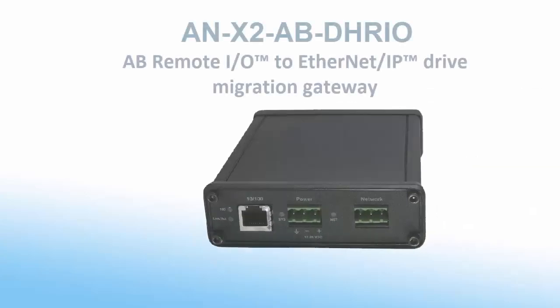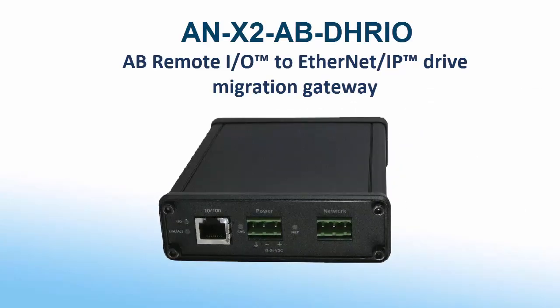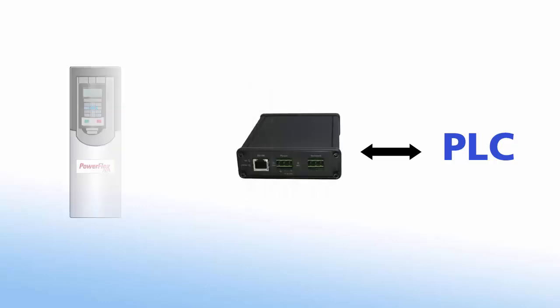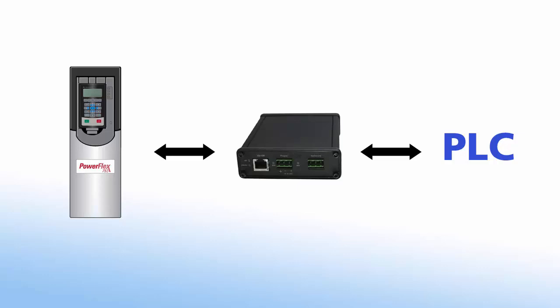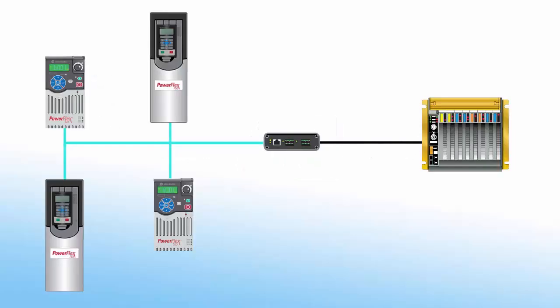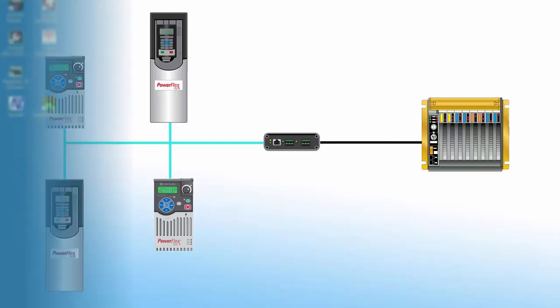In this edition, we'll be setting up the ANX2 Data Highway Remote I/O Drive Module to migrate a legacy PLC5 or SLC application with a Remote I/O Drive to a new Ethernet IP-based 753 PowerFlex drive without changing the PLC code. Each ANX2 module can communicate with up to 4 Ethernet IP drives, allowing users to replace their obsolete 1305 or 1336 remote I/O drives with new Ethernet IP drives.